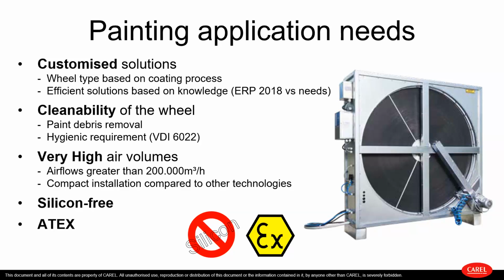Logically, as Paolo already mentioned before for the plates, silicone-free is a precondition also for the rotating heat exchangers, because otherwise the paint application would just suffer. And same as for the humidification part from Luca, we are also able to fulfill the ATEX compliance, but there's a slight difference. The rotating heat exchanger as such is not ATEX certified. This only regards the electronics, which we are able to supply to the customer adapted to ATEX.